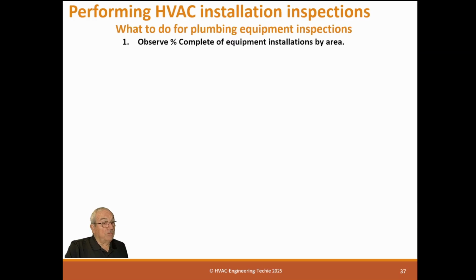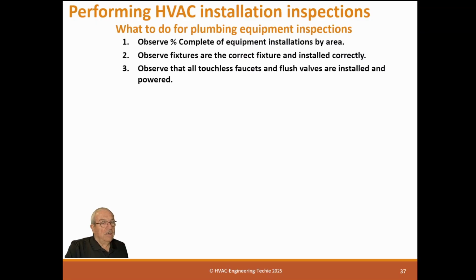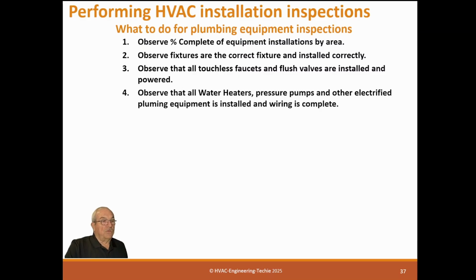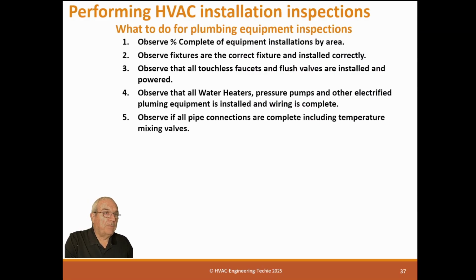What to do for plumbing equipment inspection, same thing. List percent complete by area. Observe fixtures are the correct fixtures and installed correctly. Observe that all touchless faucets and flush valves are installed and powered. Most of those are battery nowadays. They can be powered by electricity, by building power. So you just need to make sure they're done. Observe that all water heaters, pressure pumps, and other electrified plumbing equipment is installed and wiring is complete. Observe if all pipe connections are complete, including temperature mixing valves.